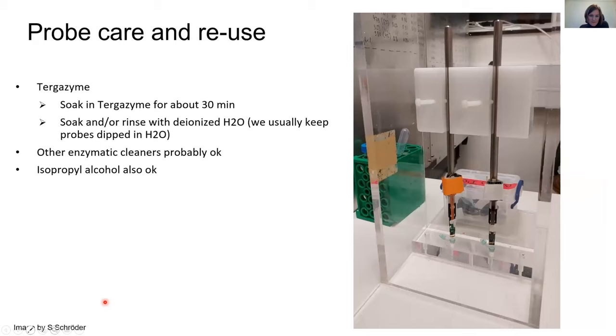At the end or after your recordings, you need to take care of your probes so you can reuse them. We cleaned them with Tergazyme, so you soak them in Tergazyme for about 30 minutes, and then soak them or rinse them with deionized water, and we used to just keep them in the water until we do the next recording. Probably other enzymatic cleaners also work. You can also clean your probes with alcohol. And that's it. That's my presentation. If you have any questions, I'm happy to answer.